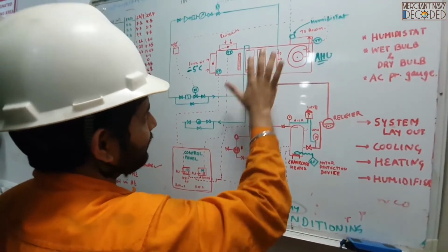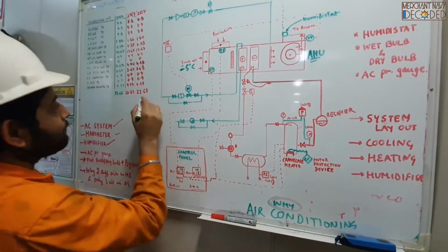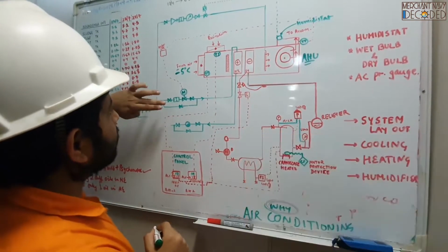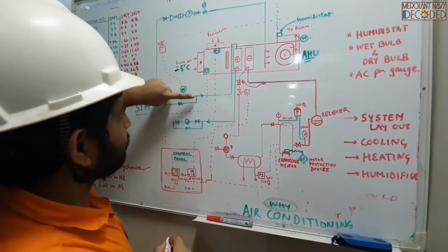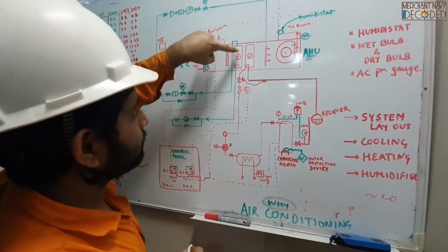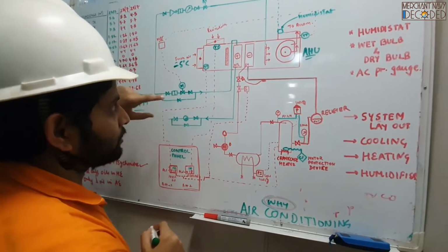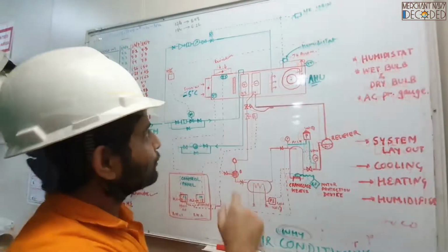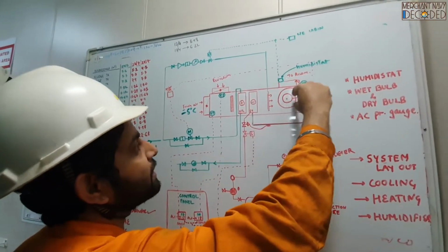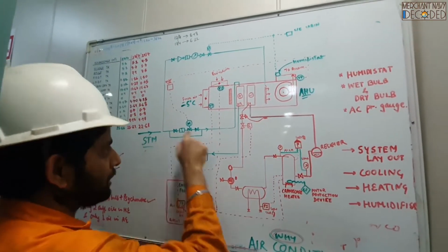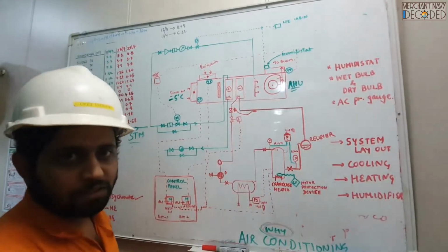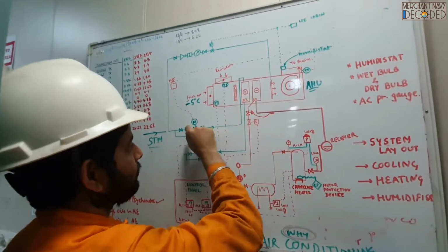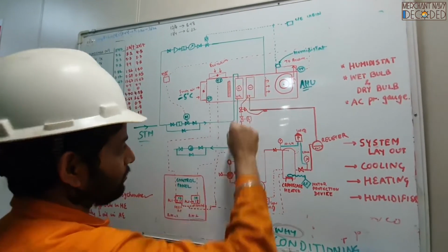This is a heater provided. Now, the steam line is over here. From here, boiler steam is coming. Steam comes over here, goes and comes back, returning in the system. What this steam is doing is heating the air when it comes. So minus 5 degrees becomes 15 degrees centigrade. You supply more steam, it becomes 20 degrees centigrade. You want it more heated, you make it 25 degrees centigrade. You give more steam over here, so it becomes 25 degrees.